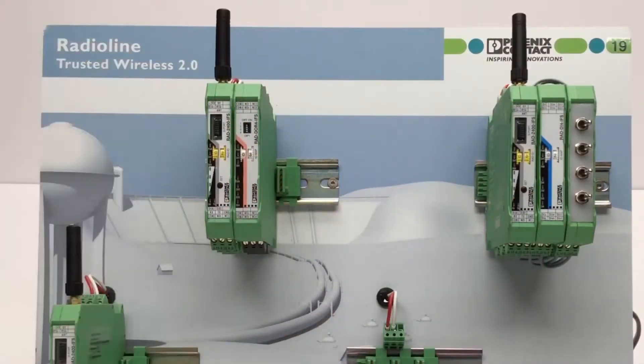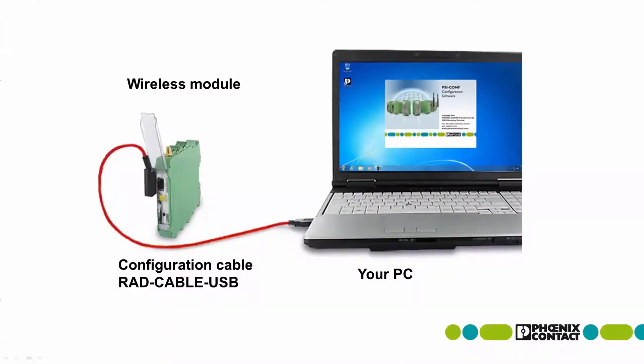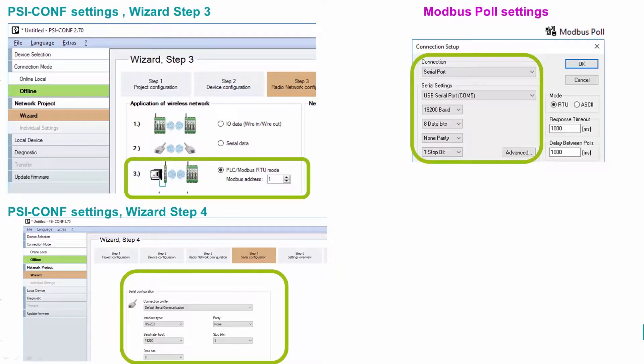A duplicate assignment of the I/O map address is not permitted unless several output modules need to receive the same command. The Modbus Poll software is used as a Modbus master on a notebook. The wireless modules must be configured with the PSI-CONF software. The devices are already pre-configured in this demo setup. The Radioline master with RAD ID 01 gets an adjustable Modbus slave address — in this setup, 01. The serial interface parameters in Modbus Poll and the wireless master must be identical.